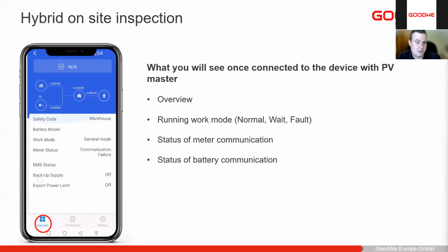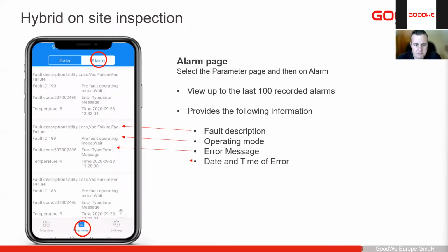Normal means it's in normal operation. Wait mode, it is waiting for something. So if there's no PV, no batteries, the device may remain in wait mode because it's waiting for a source of power. And fault mode, obviously, if it's experiencing a fault. If you go to the parameters at the bottom, and then you go to the alarms tab, so parameters, alarms, now you'll see the last 100 recorded alarms on your device. So our devices record all the alarms that happen and save the last 100.